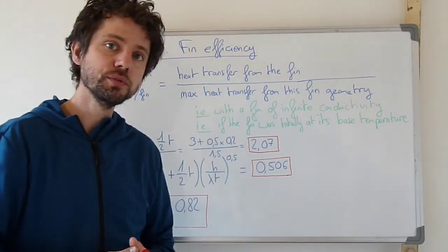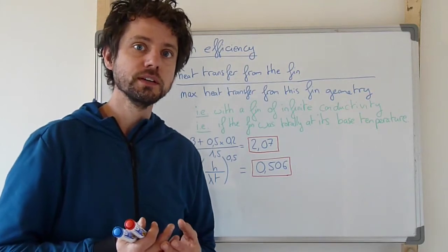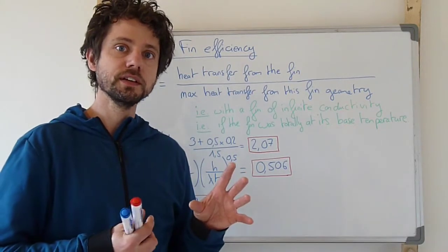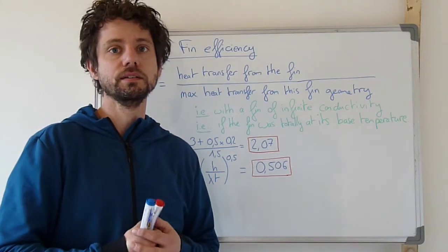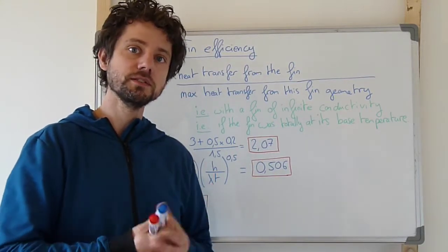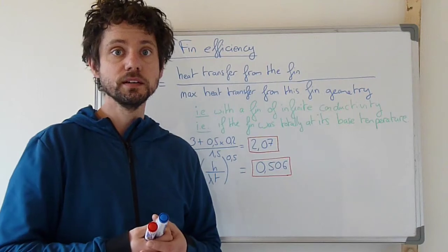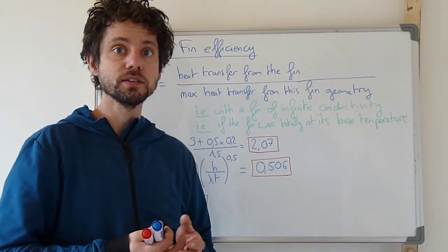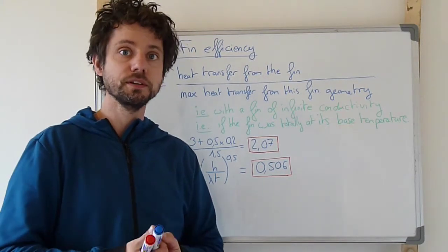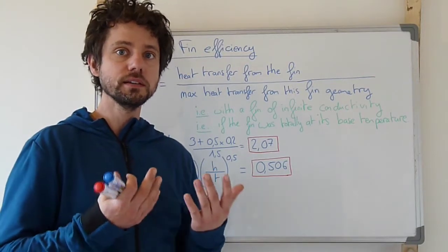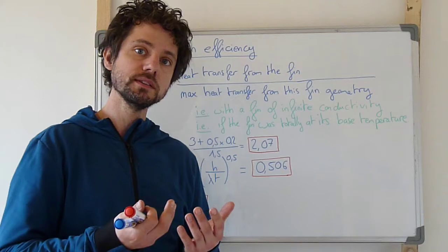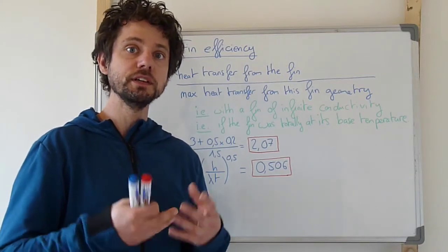In order to improve this heat exchanger, it was identified that it's the hot side, so the gas side of the convective heat transfer that is causing problems, because the heat transfer is not effective enough on this side. So in this part we try to enhance this outer surface by adding fins.